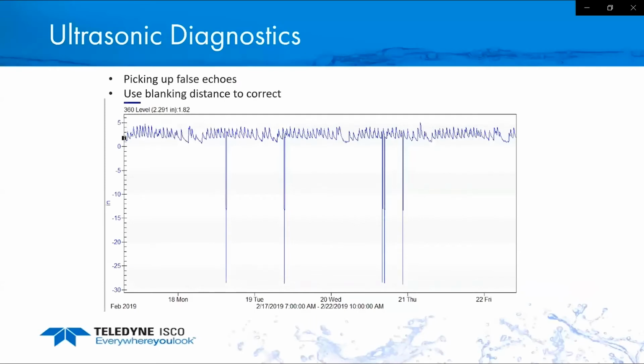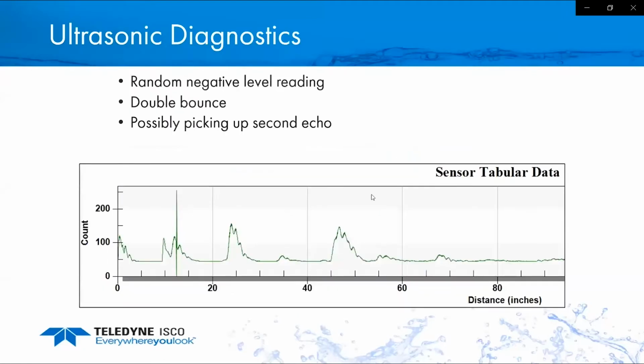Now, another thing with an ultrasonic is to look at your data. I don't like to look at just a snapshot, but at a bit more of the historical data. And what we're seeing here is that every once in a while we get these large negative spikes. What's happening is it's actually picking up a second echo, as seen here. This is the diagnostics pulled right out of the ISCO equipment, and this is the return ultrasonic signal. As you can see, it's got two different peaks. Normally it should read the first one to get our level. If for some reason the second one is higher, it would pick that one up. Because that is farther away, it ends up thinking the water level dropped, and then you end up with these spikes.